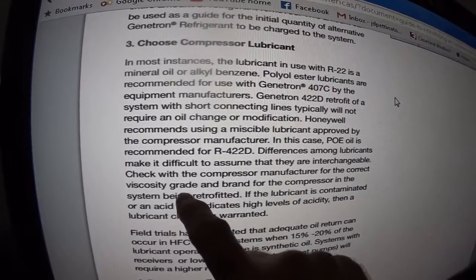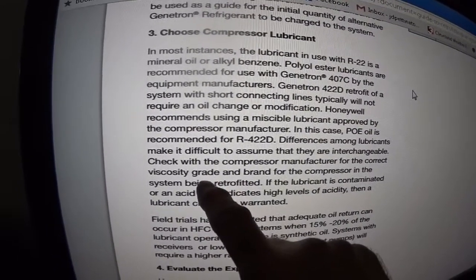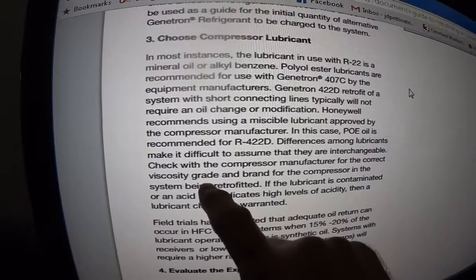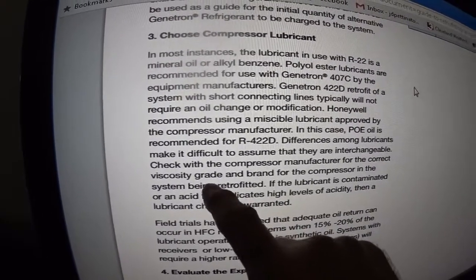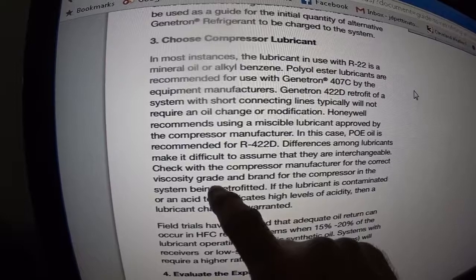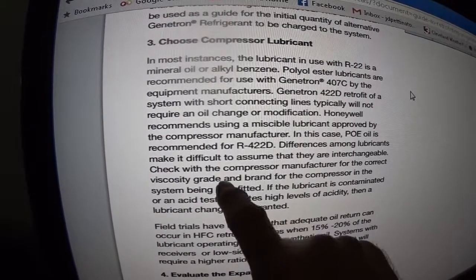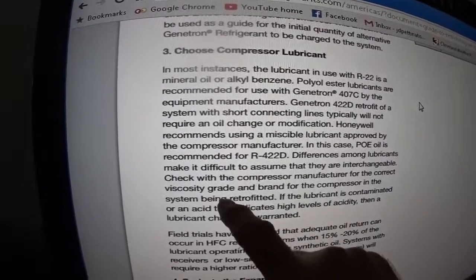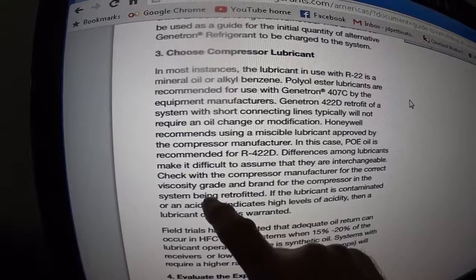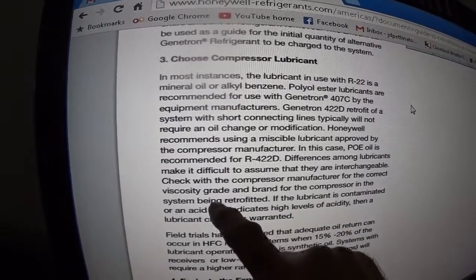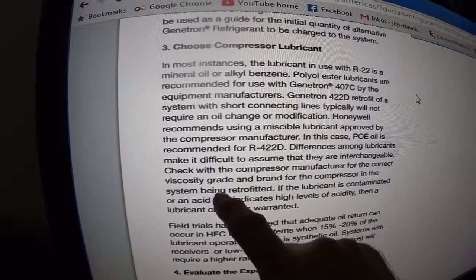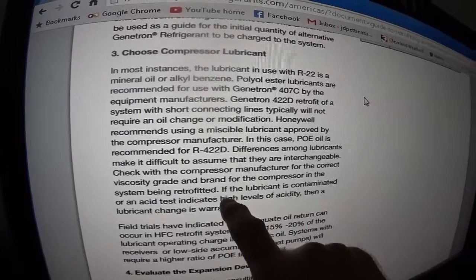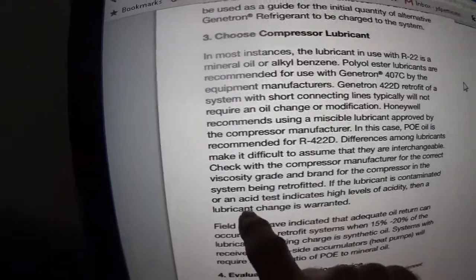The old mineral oil for medium and small refrigeration and air-conditioning equipment was Suniso 3GS, which was 150 viscosity. Alkylbenzene is also 150 viscosity, and so is POE oil. Viscosity is a lubrication factor, and no matter which oil you have in there, the lubricating factor has to be constant for the brand of compressor and system being retrofit.